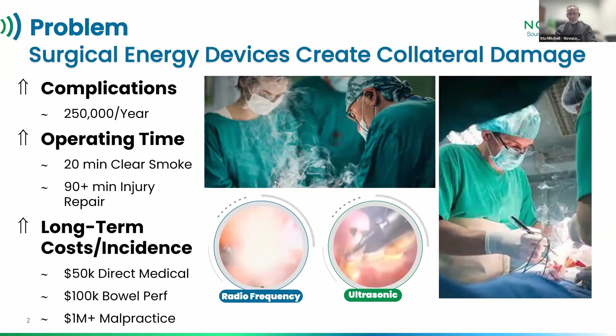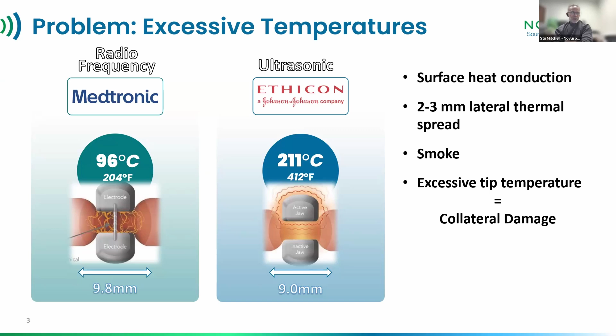These devices that are currently on the market, two main ones are the Ligasure by Medtronic and the Harmonic Ace by Ethicon. They operate at well over 100 degrees Celsius, and they operate on a principle of heat conduction, which is the most inefficient way of putting energy into tissue. It's why they burn tissue. It's why they have excessive damage and cause smoke.